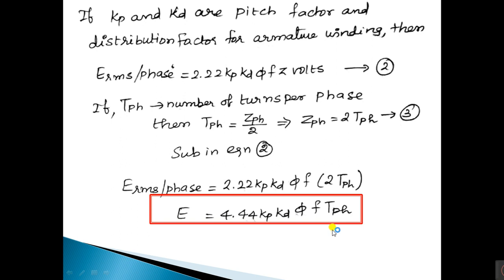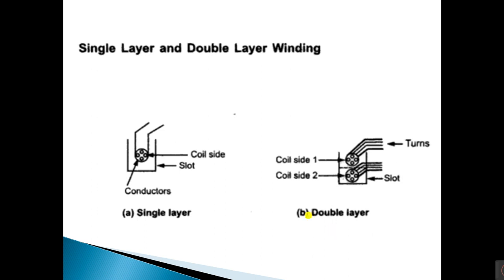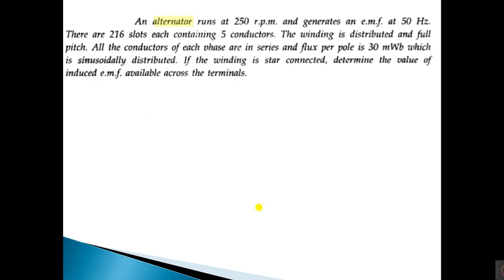You should also know the terms single layer and double layer winding. In single layer winding, a slot consists of only one coil side. In double layer winding, there are two coil sides per slot — one at the bottom and one at the top. Since a lot of space is wasted in single layer winding, double layer winding is generally preferred in practice.